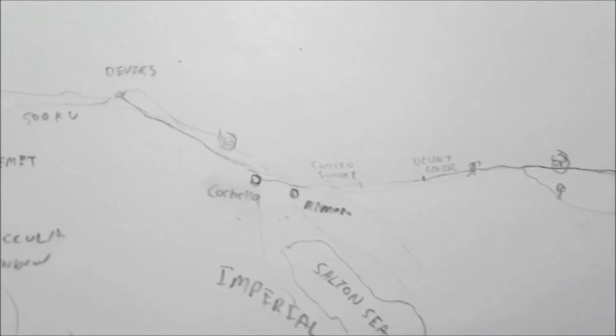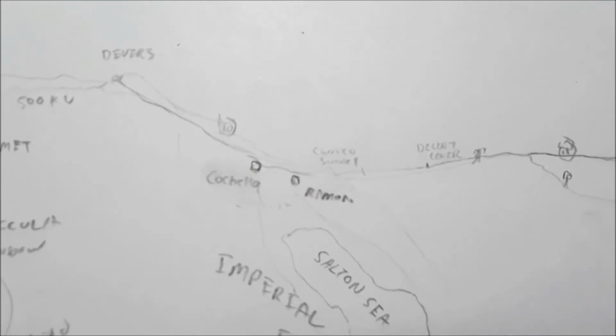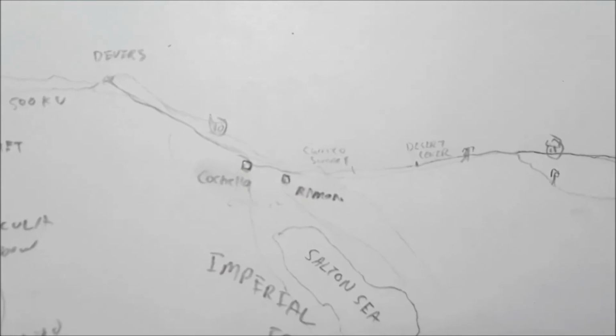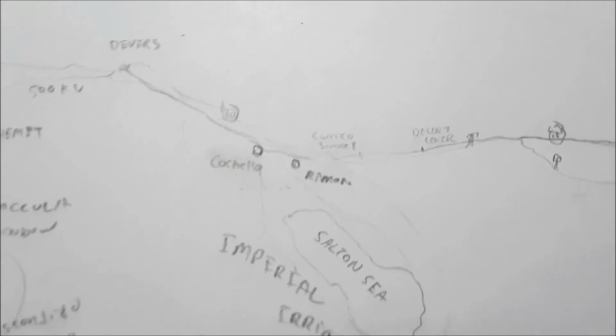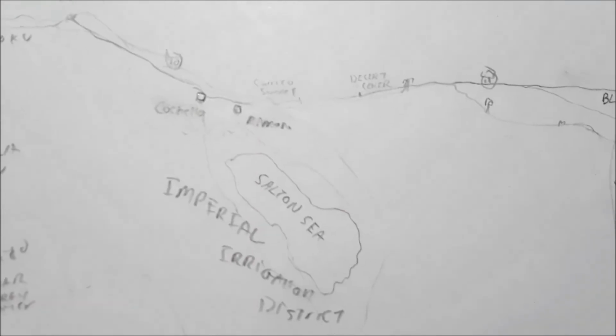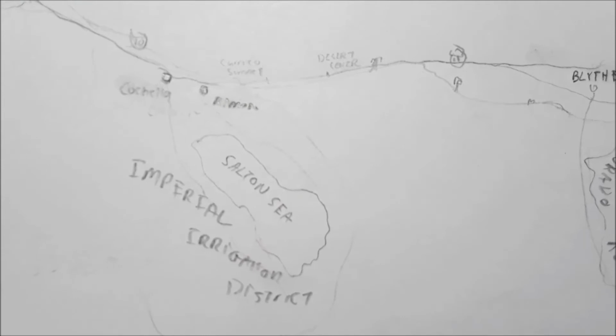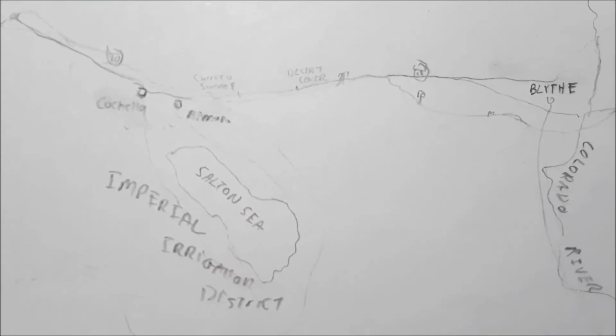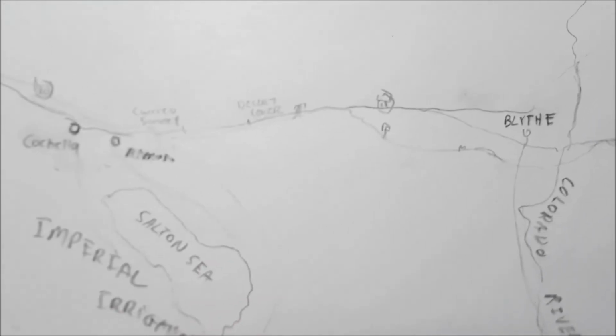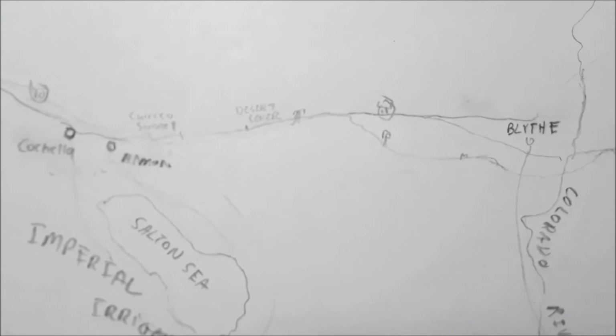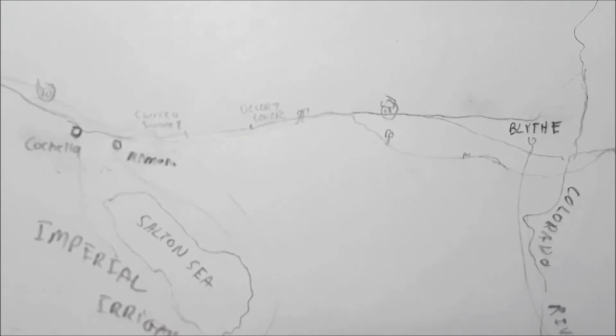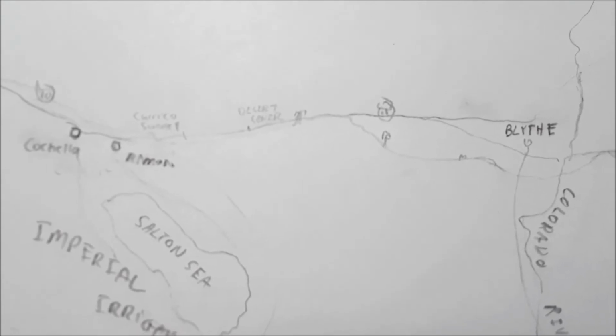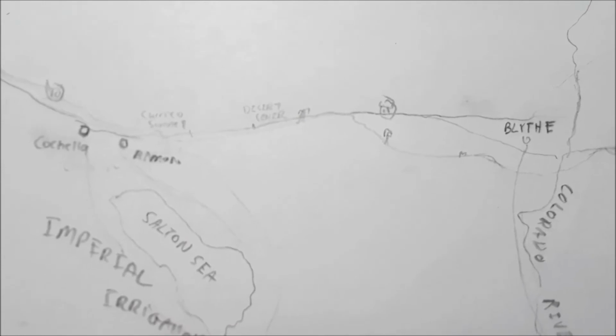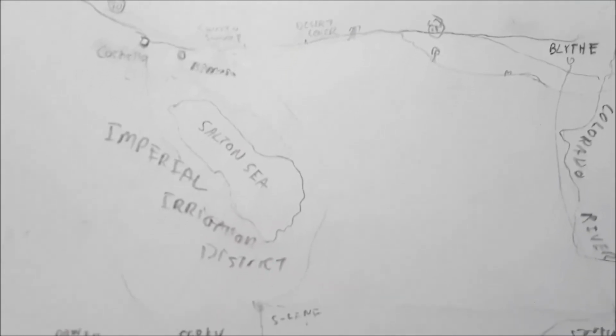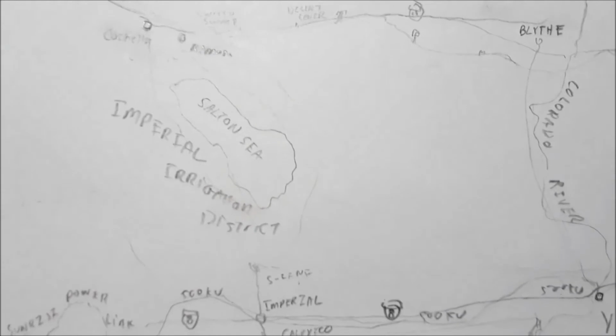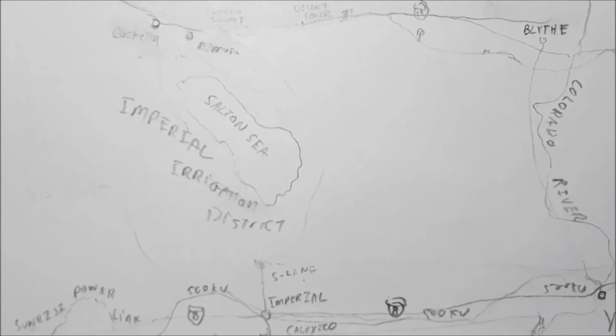In less than a minute, two transformers at Coachella Valley substation overloaded and disconnected, and this caused severe low voltages throughout Imperial Irrigation District's area. A few minutes later, another substation, Ramon, overloaded and tripped. This disconnected the majority of Imperial Valley from Southern California Edison.